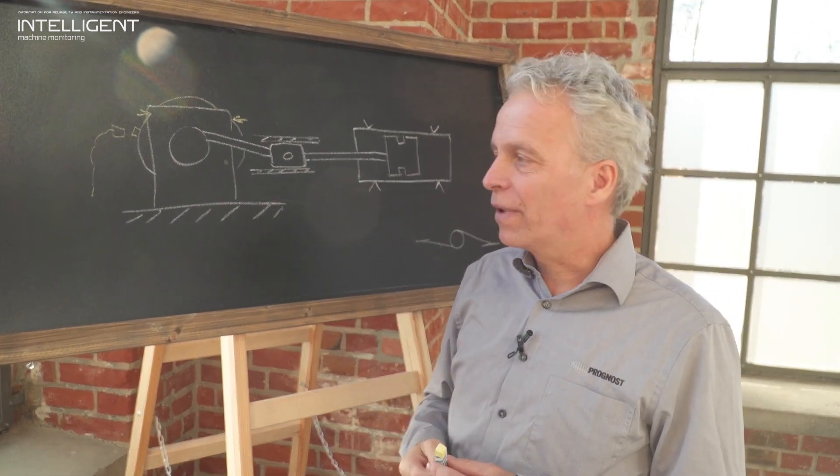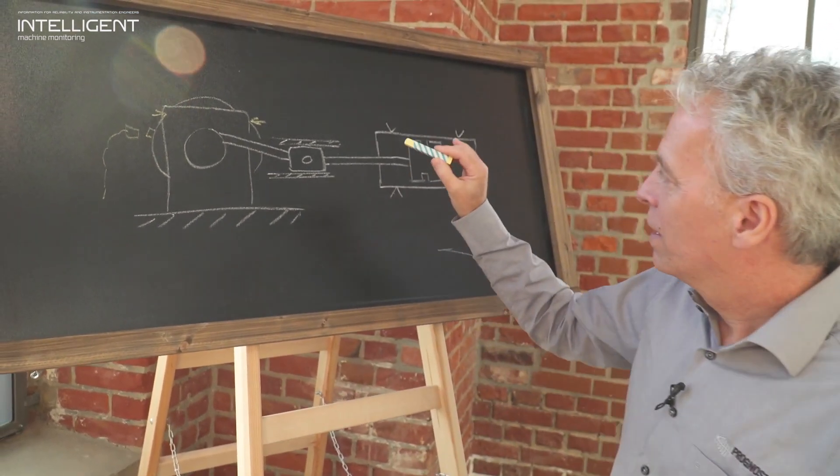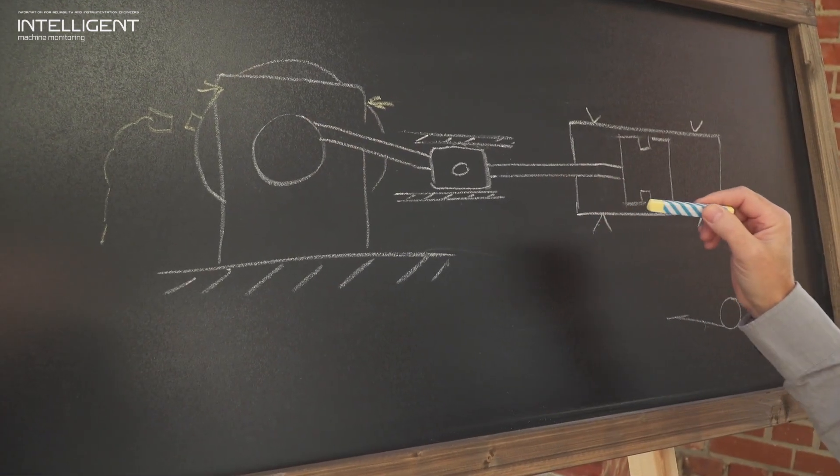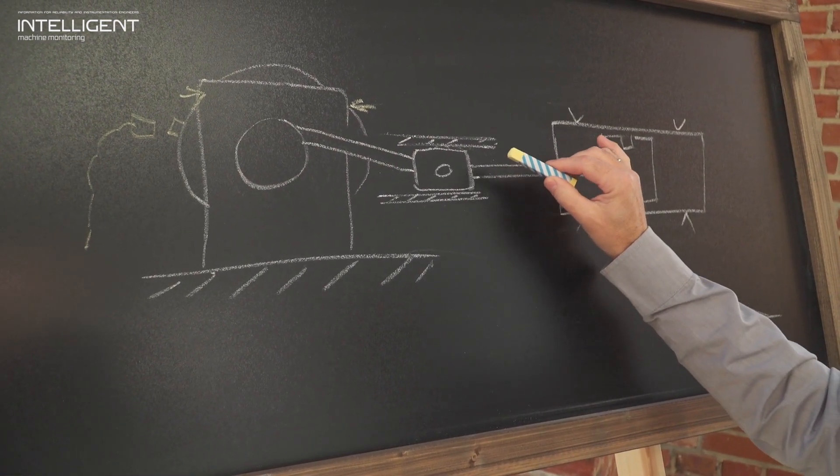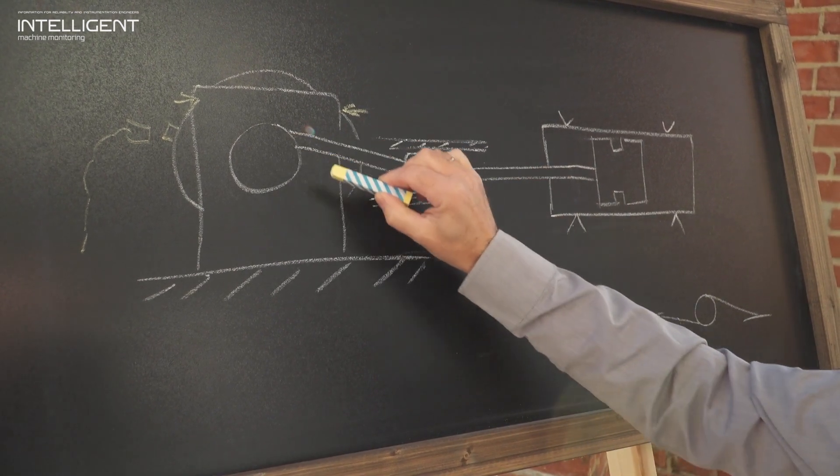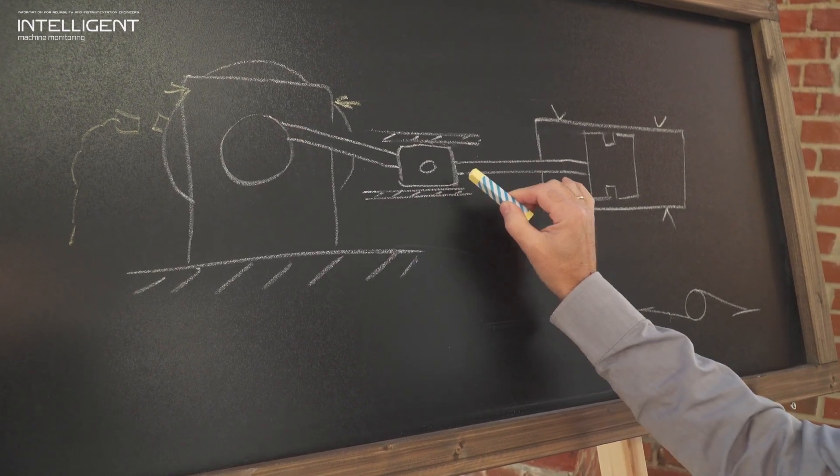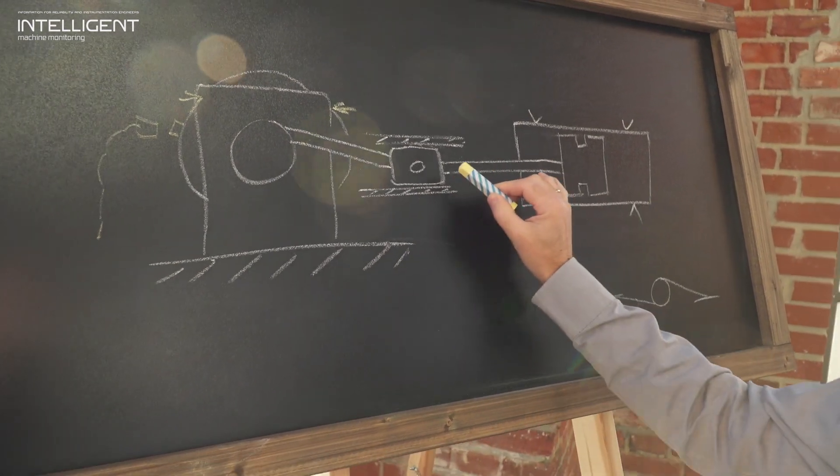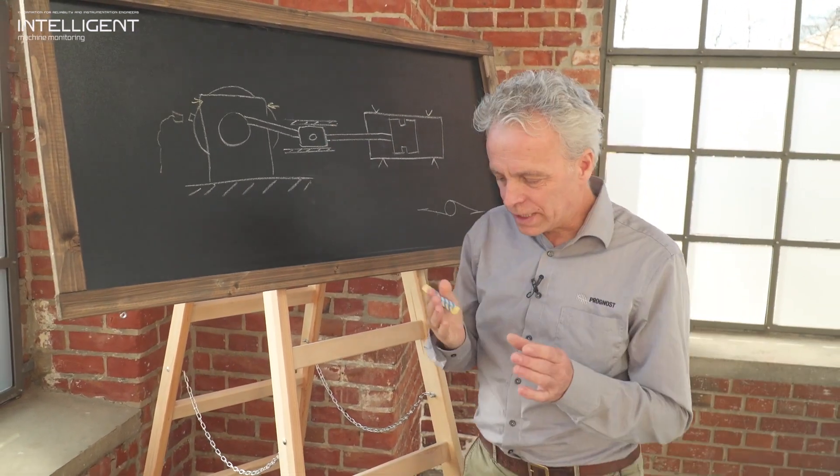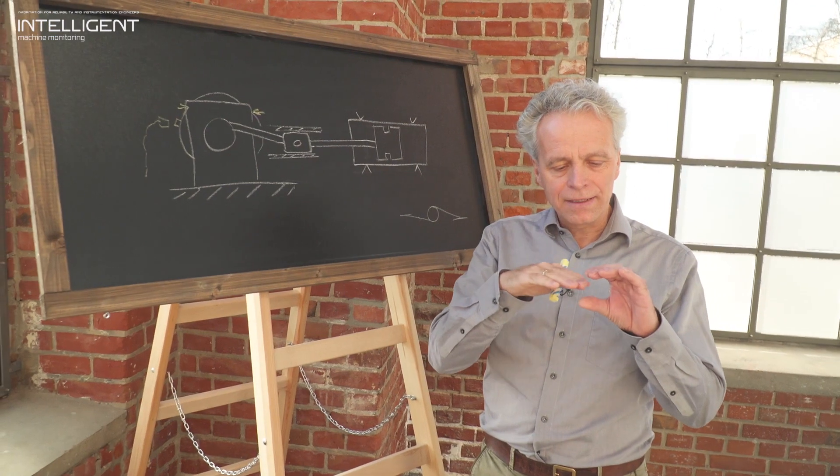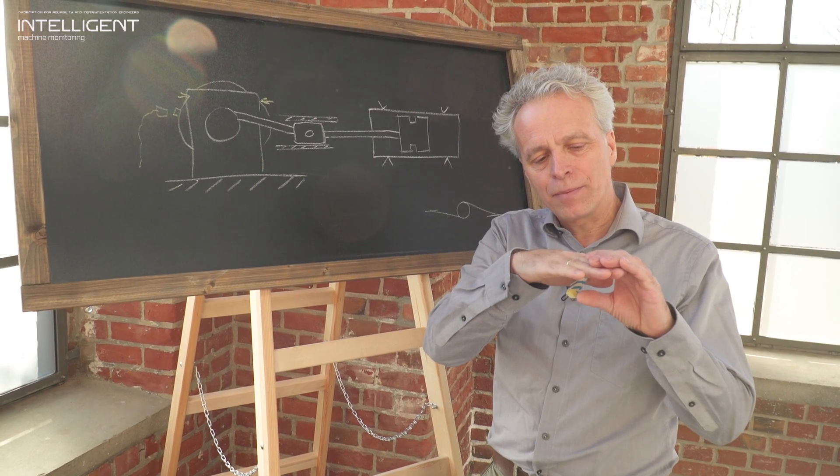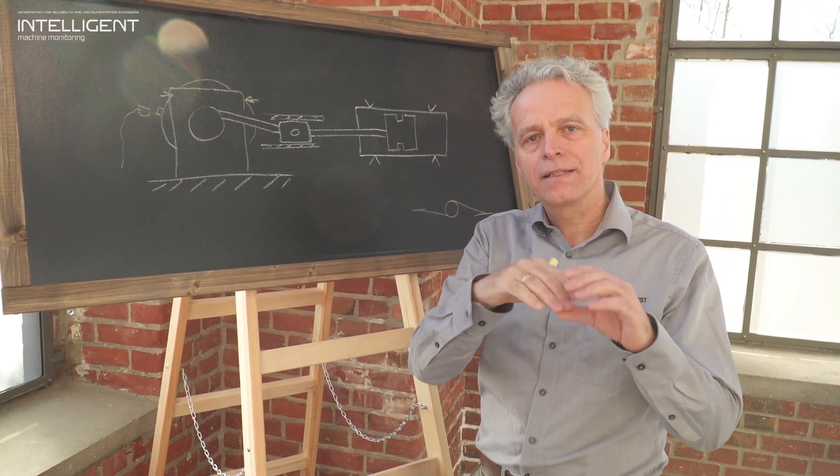Here we see the crosshead. The crosshead is one of the most critical components in the drivetrain of a reciprocating compressor because it turns the rotating movement of the crankshaft into a reciprocating movement of the piston rod and the pistons. This crosshead is supposed to move like this inside the crosshead guide.